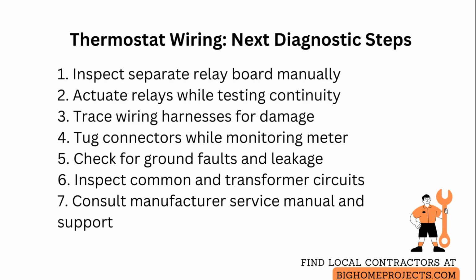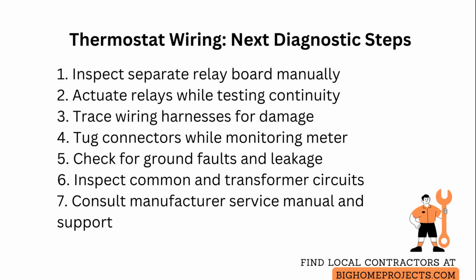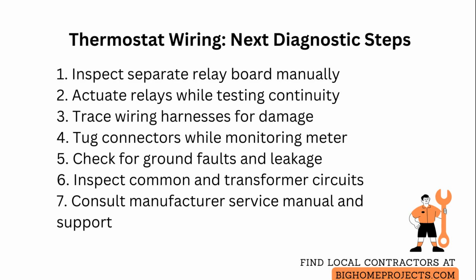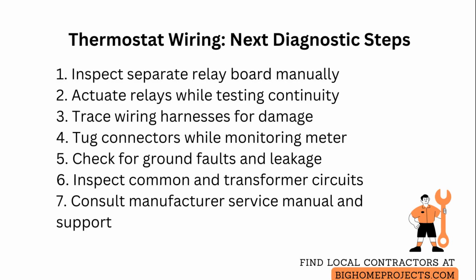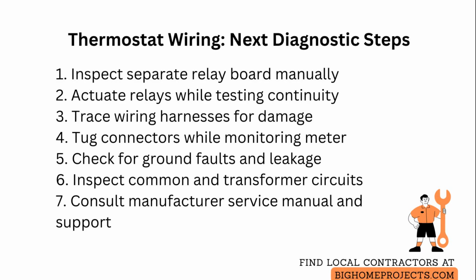Trace every wiring harness from the control board to the furnace, air handler, heat pump, and outdoor unit, looking for chafed insulation, loose terminals, or intermittent breaks that only show under vibration. Gently tug each connector and wiggle wires while watching your meter for changes.